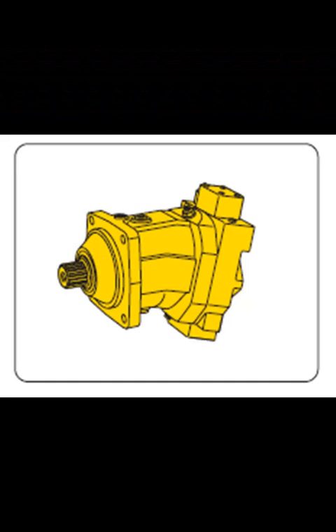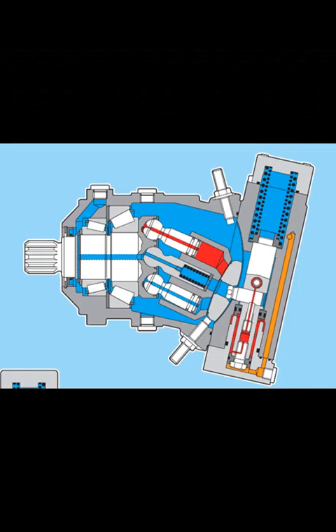LR Constant Power Control: The constant power control controls the output volume of the pump in relation to the working pressure so that, at a constant drive speed, the preset drive power is not exceeded. pB × Vg equals constant, where pB equals working pressure and Vg equals pump displacement. Optimum power usage is obtained by accurately following the power hyperbola.